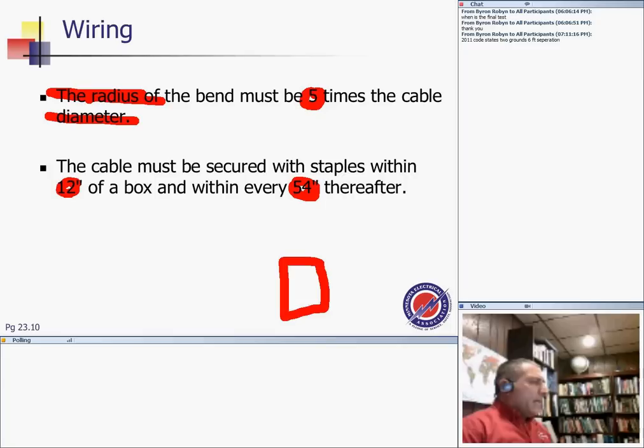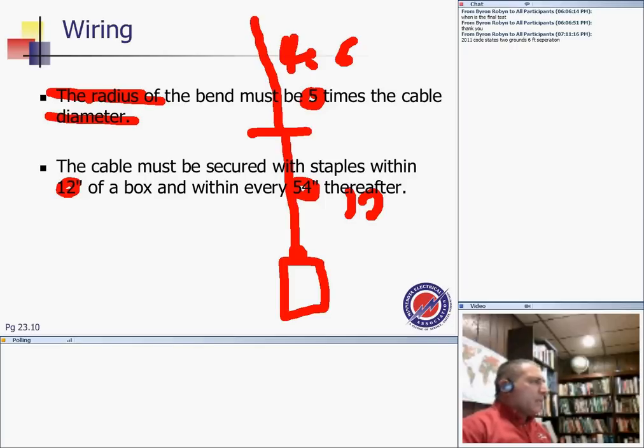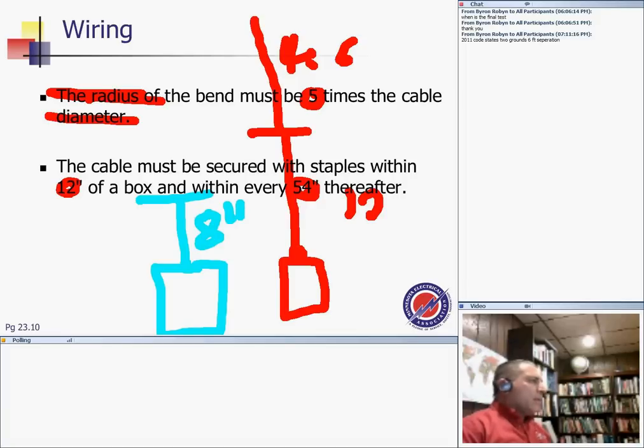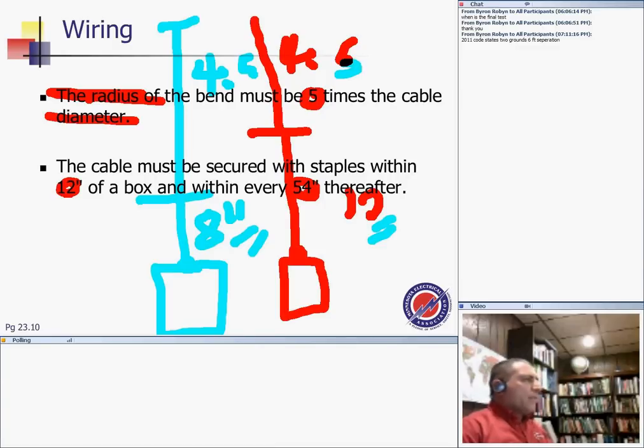My box over here, I have a strap in here. Go all the way up to 12 inches, and after that 4.5 feet. Now they catch you on the NEC code book, guys. They say, what if you have a receptacle? If you have a non-metallic box and you don't have a strap because the hole is broken here, it goes all the way down to 8 inches. Please put a note here. You go down to 8 inches, guys. This is the same, 4.5. If you have a non-metallic box and the cable doesn't have a strap here, of course, it's broken, just the hole goes through it, then it goes down to 8 inches. That's kind of an exception. 4 inches to 12 inches. Write a note for that for the journeyman exam.